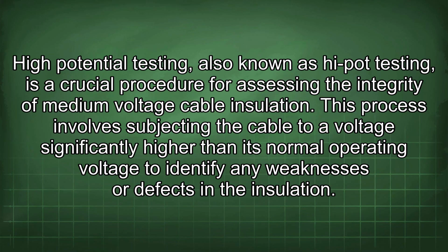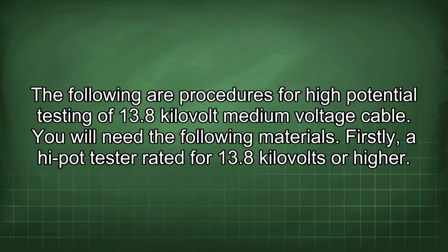High potential testing, also known as hi-pot testing, is a crucial procedure for assessing the integrity of medium voltage cable insulation. This process involves subjecting the cable to a voltage significantly higher than its normal operating voltage to identify any weaknesses or defects in the insulation. Following are procedures for high potential testing of 13.8 kV medium voltage cable.